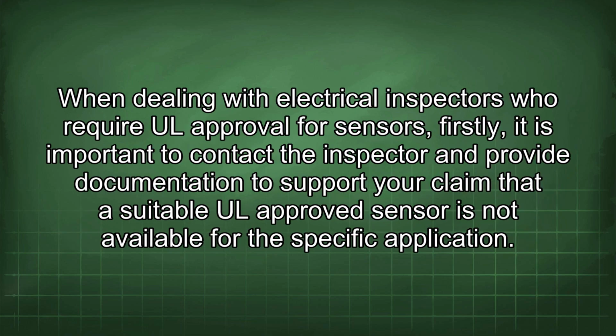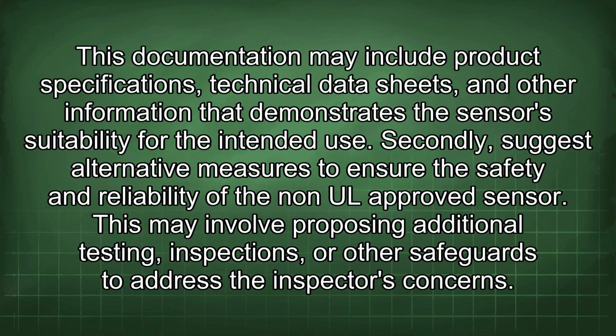When dealing with electrical inspectors who require UL approval for sensors, firstly, it is important to contact the inspector and provide documentation to support your claim that a suitable UL-approved sensor is not available for the specific application. This documentation may include product specifications, technical data sheets, and other information that demonstrates the sensor's suitability for the intended use. Secondly, suggest alternative measures to ensure the safety and reliability of the non-UL approved sensor. This may involve proposing additional testing, inspections, or other safeguards to address the inspector's concerns.